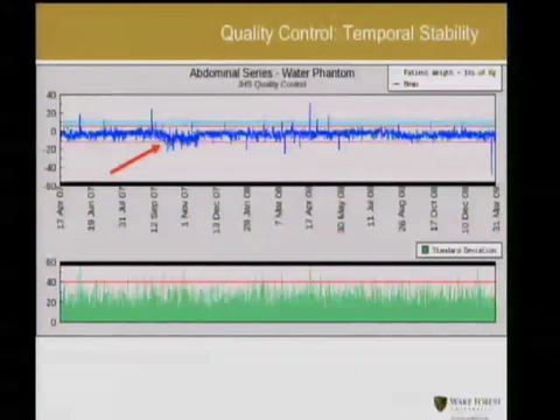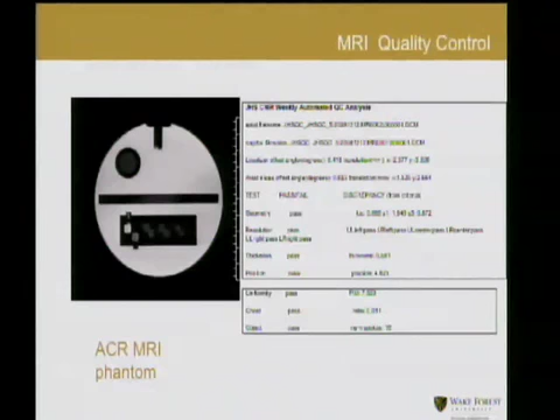And so I am going to do a gratuitous plug for one of the projects that I would like to collaborate on with your team here, and that's for MRI calibration. We've developed for the Jackson Heart Study this automated QC analysis that tracks temporal drift for MRI scanners using the ACR accreditation phantom. You send us the DICOM images. It automatically identifies the objects and measures them, and allows us to develop an automatic pipeline that looks at geometry, ghosting artifacts, and homogeneity within a given MR scanner.